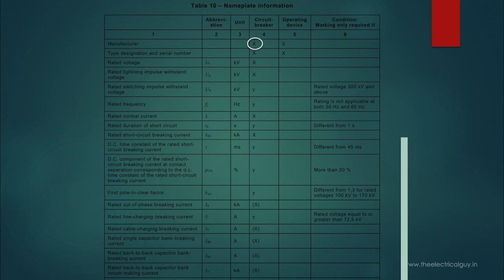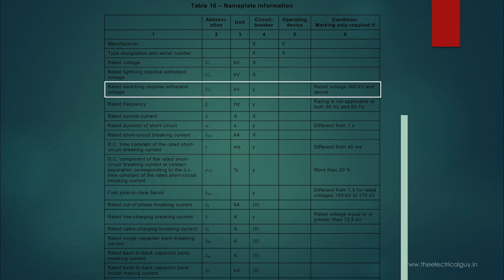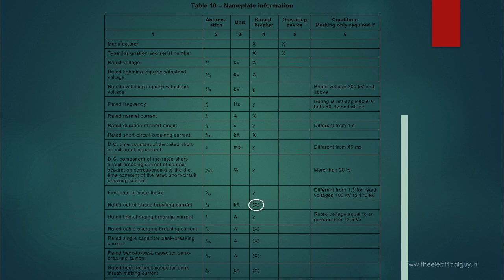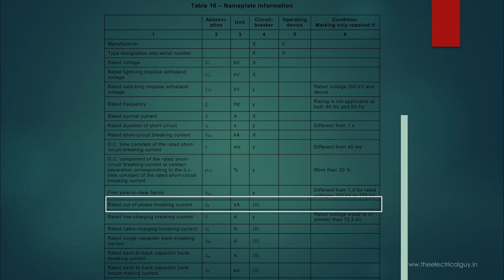Some of these parameters may be skipped if mutually agreed between manufacturer and customer. Parameters marked with Y are based on the condition stated in column 6 — if the breaker satisfies that condition, the parameter must be on the nameplate. For example, rated switching impulse withstand voltage is only applicable for circuit breakers rated above 300 kV. Parameters marked with X in brackets are totally optional — one manufacturer may include them and another may not. For example, rated out-of-phase breaking current is completely optional.